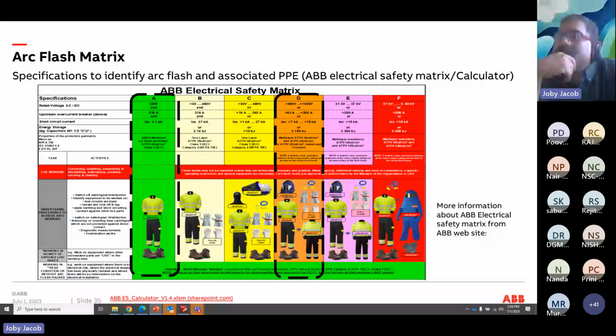So for example, if you are working in a completely green field in a de-energized environment, but inside a substation or in a dangerous factory environment, we still prefer that our employees wear arc flash PPE as a base minimum, so that you are working in an energized or substation environment. So there could be some sort of dangers. The basic minimum PPE should be category 2. I will come to that actually. So they get a basic, that is like a uniform. It is not like olden times where you needed to wear cumbersome boiler suits or something like that. Instead of wearing a normal coverall, you protect them with an arc flash coverall. And nowadays the cloth materials are also improved, so you get the basic minimum protection.